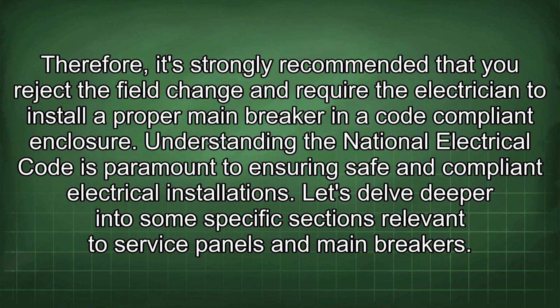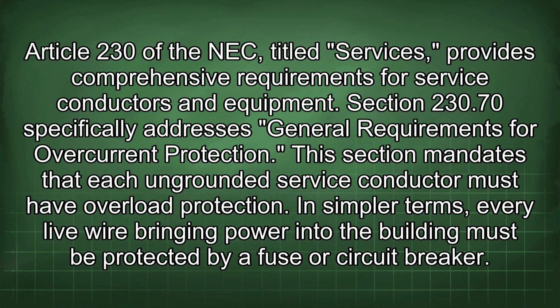Let's delve deeper into some specific sections relevant to service panels and main breakers. Article 230 of the NEC, titled Services, provides comprehensive requirements for service conductors and equipment. Section 230.70 specifically addresses general requirements for overcurrent protection. This section mandates that each ungrounded service conductor must have overload protection. In simpler terms, every live wire bringing power into the building must be protected by a fuse or circuit breaker.